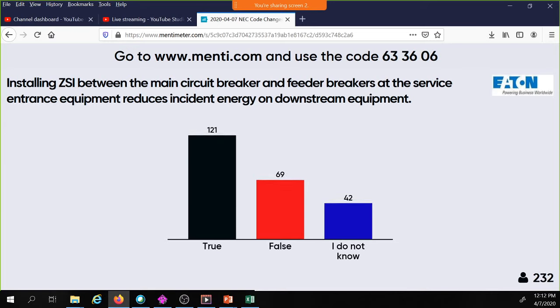ZSI, think about that first word, zone. You have a zone of protection. If anybody played football or basketball, any of these sports, you had a zone. If something happened outside of your zone, did you get blamed for it? No, because you were working a zone, and you can't take credit. You can't help things that don't enter your zone of what you're doing. And that's what zone selective interlocking is.